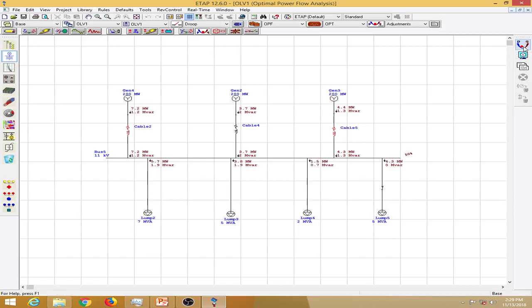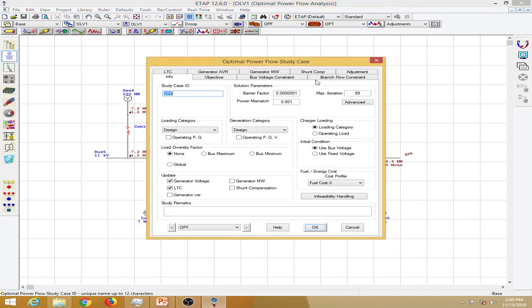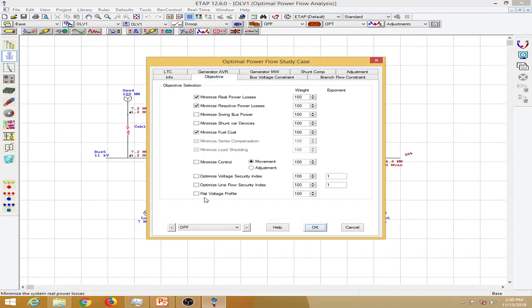Running the optimal load flow, generator 4 is delivering most of the power at 7.2 megawatts, with 3.7 megawatts and 4.4 megawatts from the others. Generation has been optimized based on economic constraints. However, looking at the voltage at a particular bus it is at 50%, so we need to add voltage constraints as well.